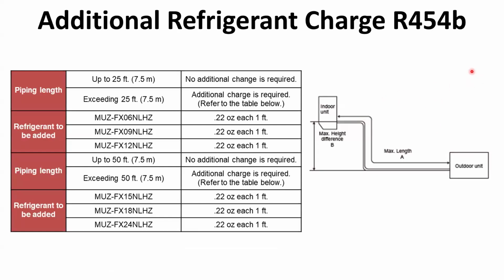Again, this has been trimmed down to take some of the features of each unit, like the submittal already shows. So rather than talk about what's in the submittal, which you can get from the website, we trimmed this up a bit and made it more focused on technical and installation, etc. So again, additional refrigerant charge for R454B. If you're looking at this, we're just talking about the one-to-one systems right here. Pipe length: up to 25 feet, no additional charge required. If you're exceeding that 25 feet, you're going to have some type of additional charge.